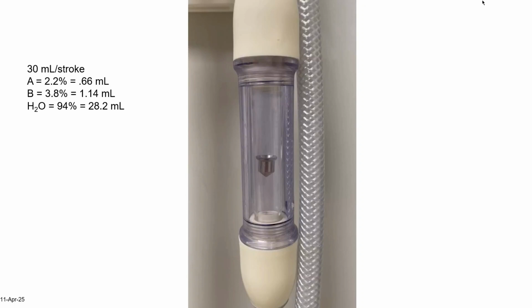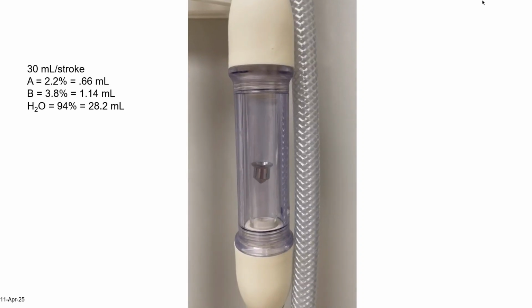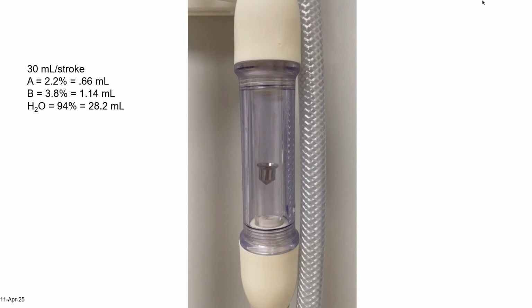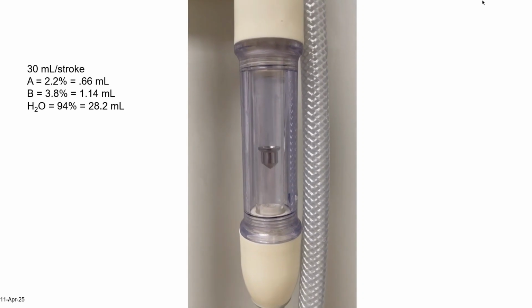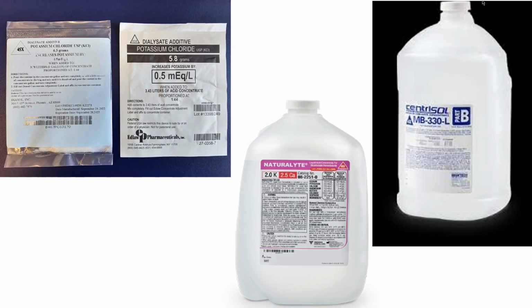So that's the movement. So you've got 2.2% of your dialysate is acid, which is 0.66 ml. And your bicarbonate is 3.8%, which is 1.14 ml. And your water, your RO water, is 94%, which is 28.2 ml. So actually, this happened. See, you don't notice that there's actually no flow. It's just a slight drop. Okay.